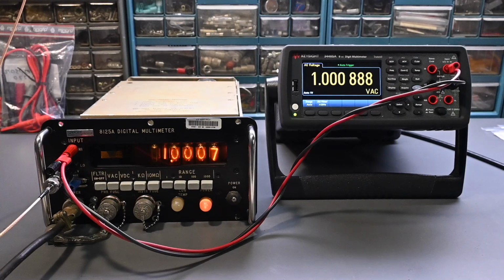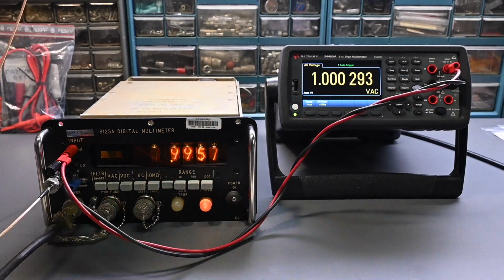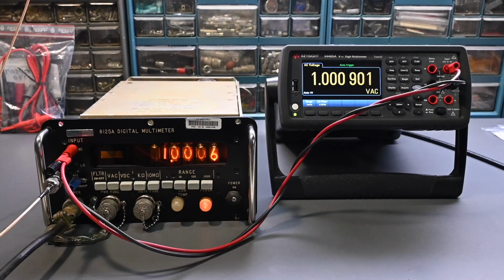If we go over here to frequency, and I'll go to 60 hertz. So 1 volt at 60 hertz, again, very close, basically within agreement over there to the Keysight within a couple counts. And if I go to 20 kilohertz, so that's 1 volt at 20 kilohertz. No problems there, spot on. I mean, it's in exact agreement with the Keysight.